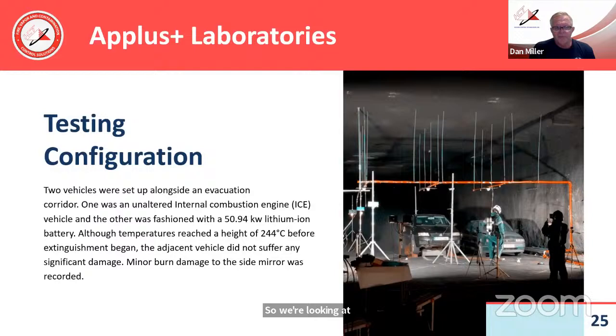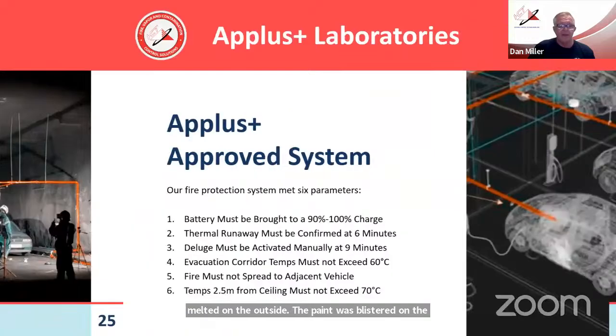So it was a 50.9 or 51 kilowatt hour battery, basically. It was a lithium-ion battery. The temperatures reached a height of 244 degrees Celsius before extinguishment began. So there was some pre-burn time to make sure it was in thermal runaway. And in the testing, the adjacent vehicle didn't suffer any significant damage. The mirror was burnt, the mirror was melted on the outside. The paint was blistered on the outside, but the vehicle next to it never did catch fire.